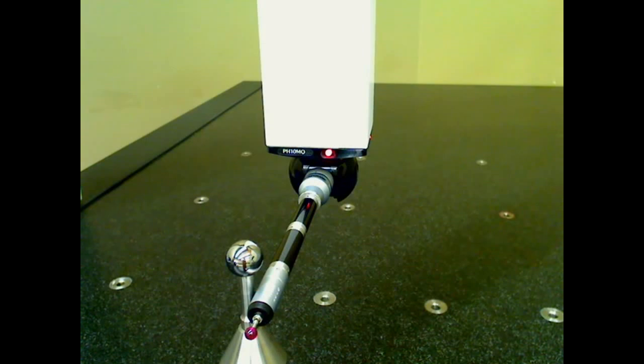Let's look at a quick way to verify the squareness between the PH10MQ's head and the CMM's y-axis. The first thing you want to do is put a longer probe extension on there so that we can have something to gauge the squareness against.